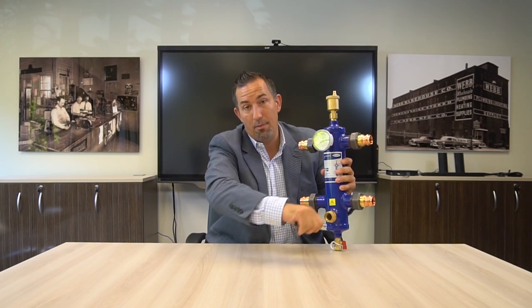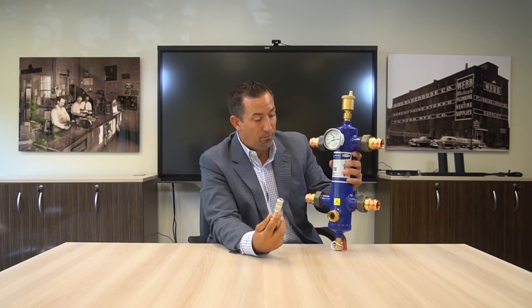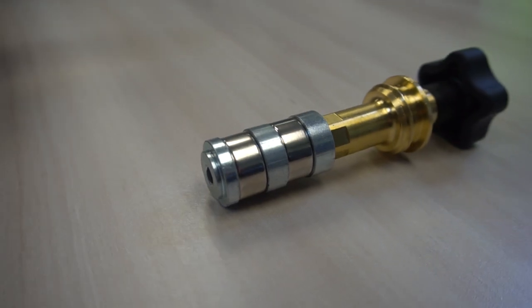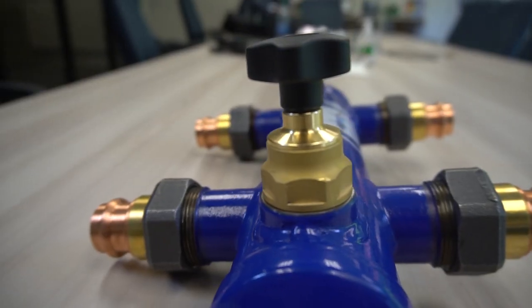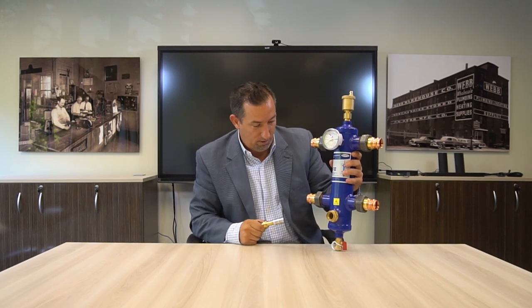Ferrous materials and magnetite is something that's talked about very frequently in today's high efficiency hydronic world. Magnetite is the number one problem in high efficiency boiler systems today. A recent study just showed that 95% of all boiler system failures can be attributed to magnetite in some way. This is a 10-pound rare earth magnet designed to go in this well, and we remove 100% of all ferrous materials.